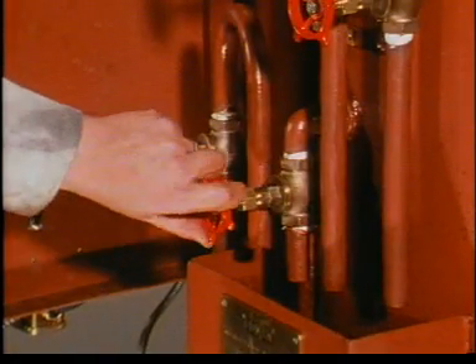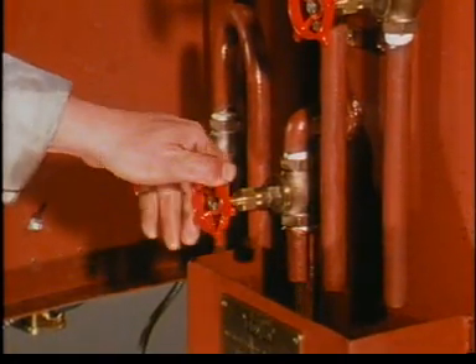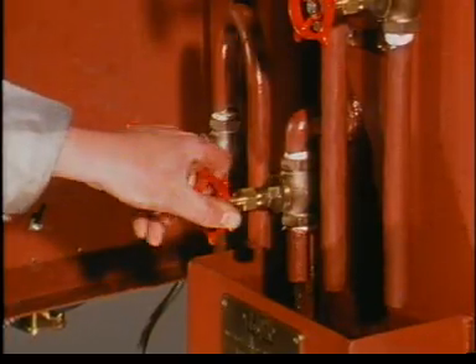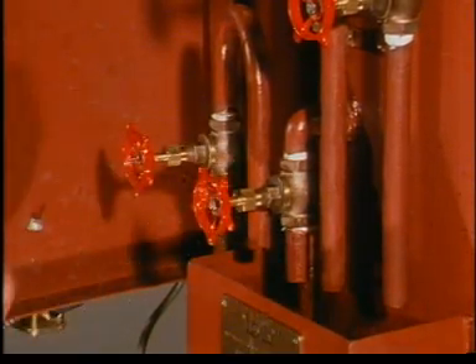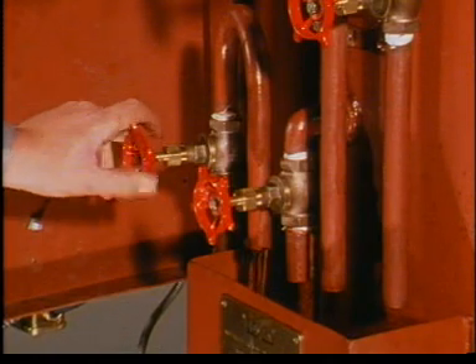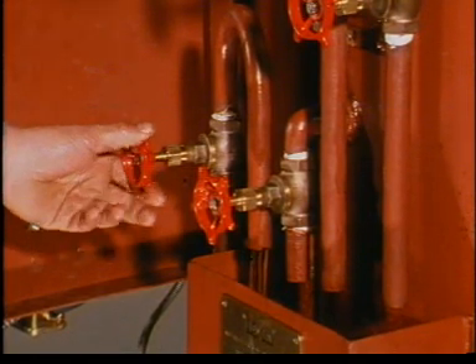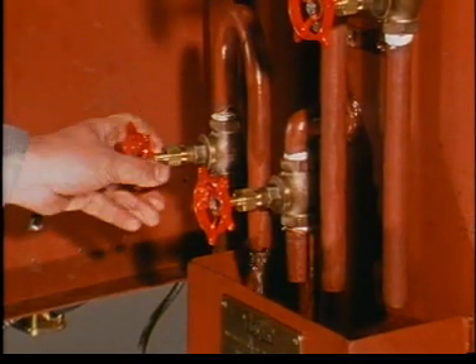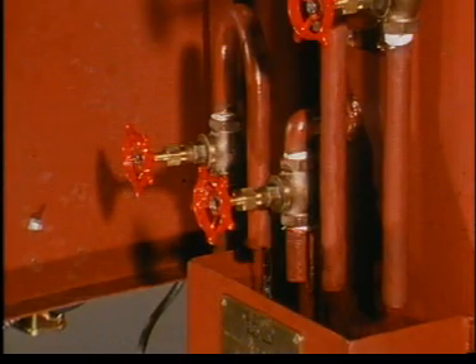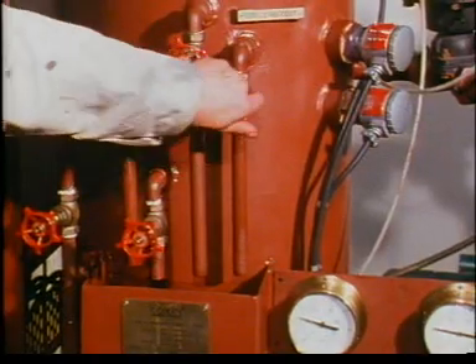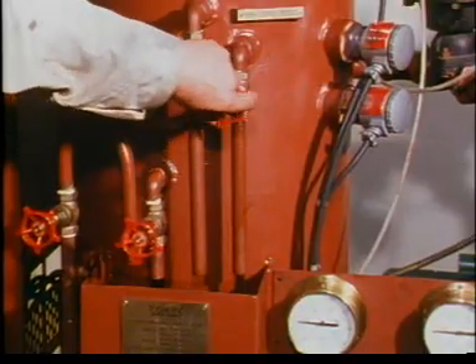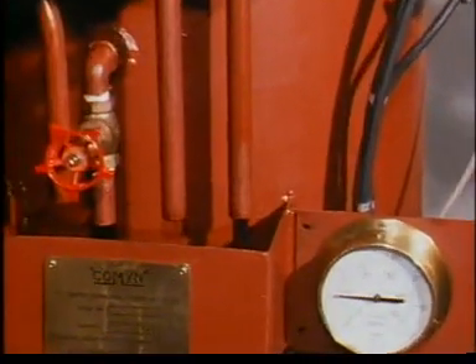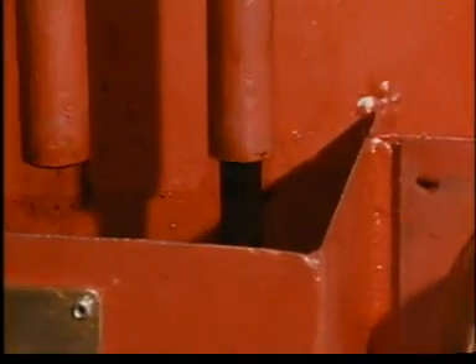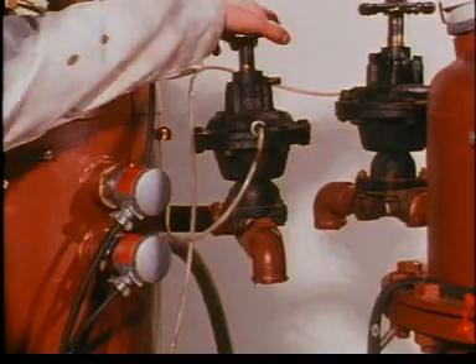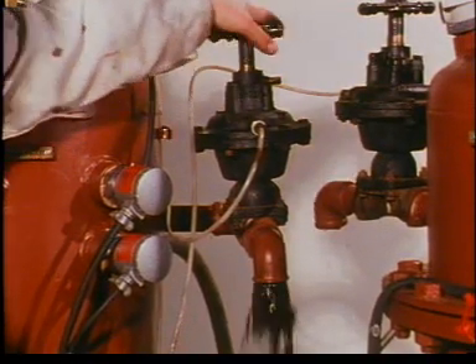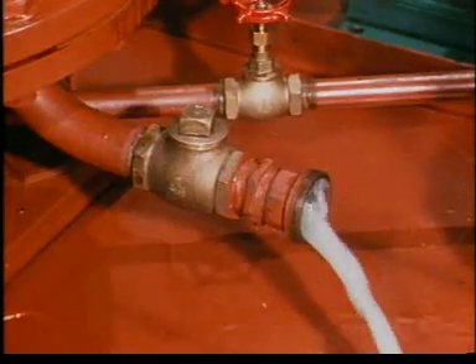This test valve is connected direct to the oily water inlet pipe and enables a visual estimate of its oil content to be made. Finally, this test valve is connected direct to the water discharge system and enables a similar visual check to be made. When oil flows out of the low-level valve, it means it's time to open the oil outlet valve and drain the collected oil. The opening of this valve reduces the pressure in the system and the spring-loaded water outlet valve closes automatically.